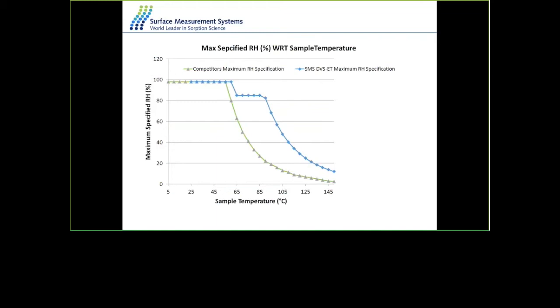Comparing the SMS system to competitor systems, you can see the green line for the competitor and the blue line for the SMS system. At above 60°C, competitor systems are unable to maintain relative humidity, whereas with our system you can still maintain over 80–85% relative humidity even at higher temperatures.